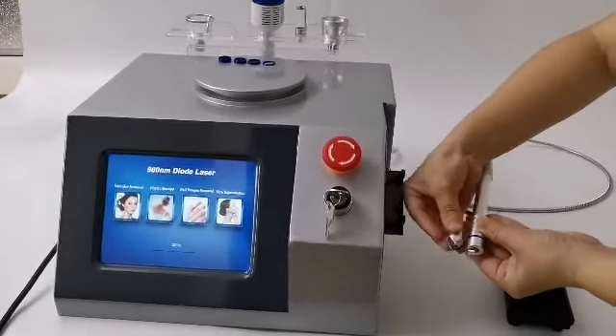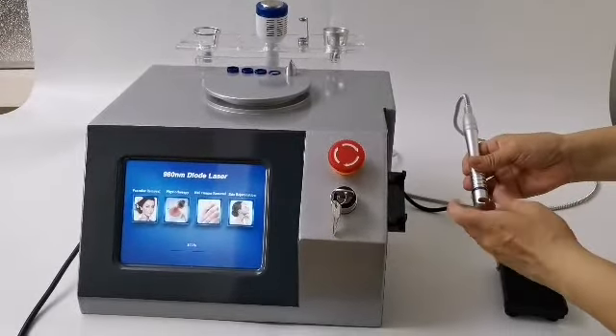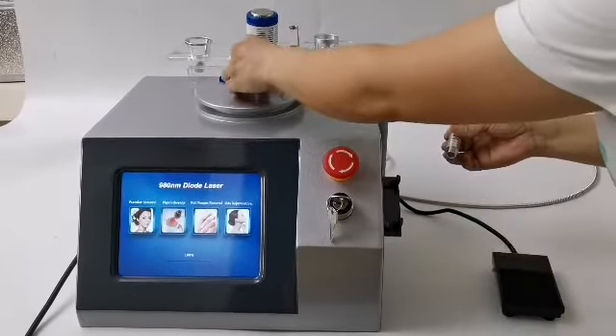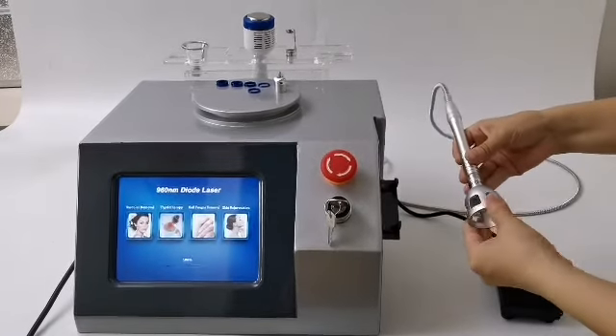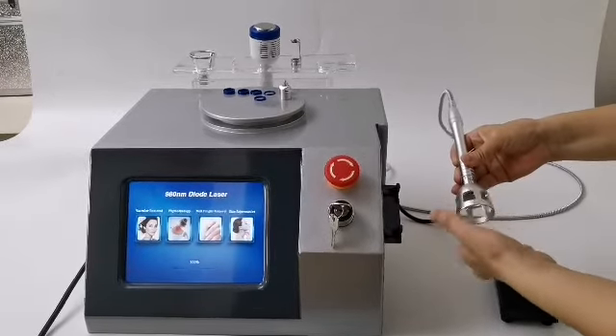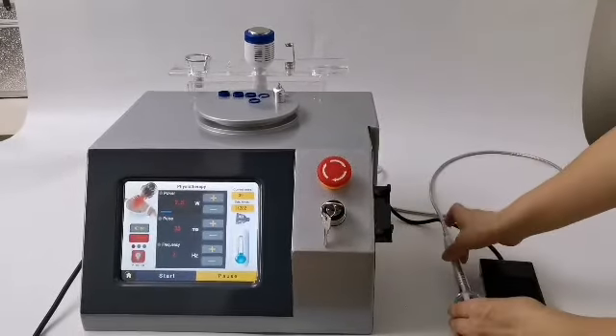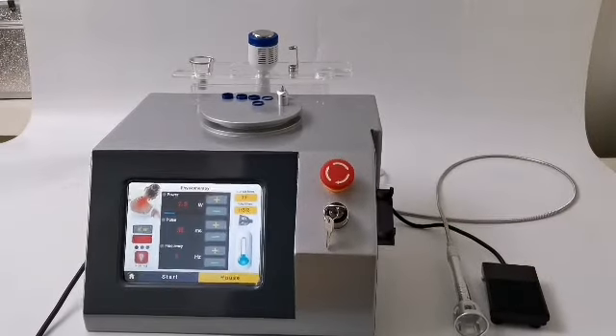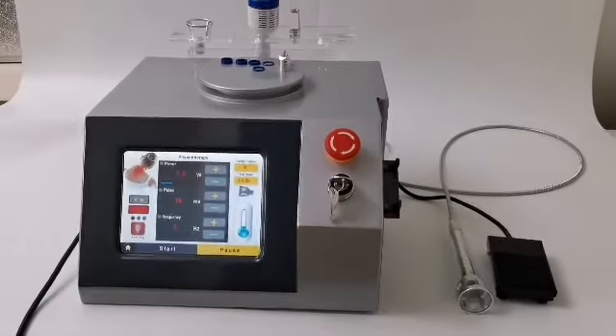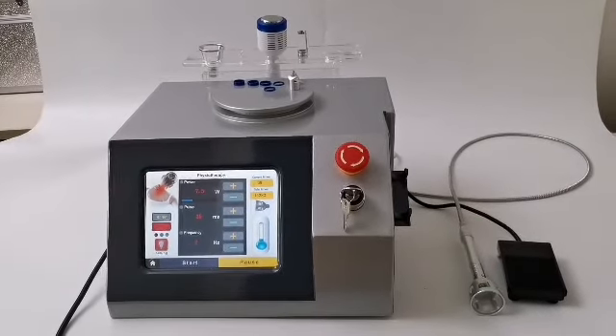When using the red blood vessel treatment head, which is used to remove red blood vessels, the most commonly used focusing ring is 0.5 mm. If the red blood vessel is thick, then change to the thin focusing ring. When pain therapy is needed, the pain treatment head is needed to replace it, without the focusing ring. Enter the operational interface of the pain physiotherapy. The interface operation method is the same as the operation of red blood vessel removal.